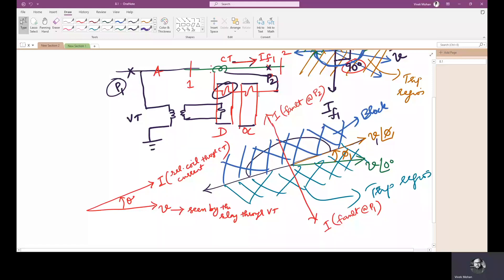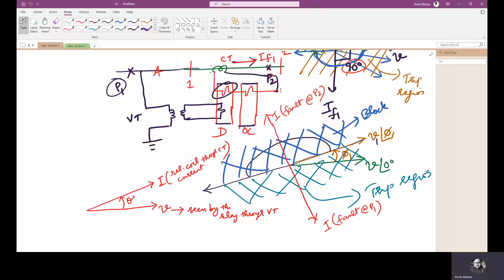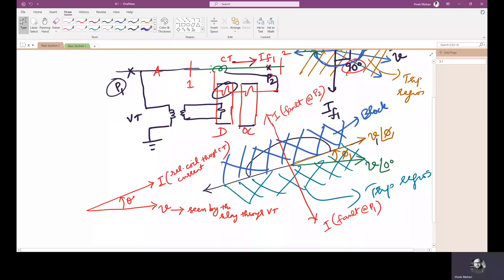The second condition is the overcurrent condition — the magnitude of current should be greater than the pickup value. So, the magnitude of current should be greater than the pickup value and the direction of current should be in the tripping direction, which corresponds to the trip region of the relay and not the blocking region of the relay.